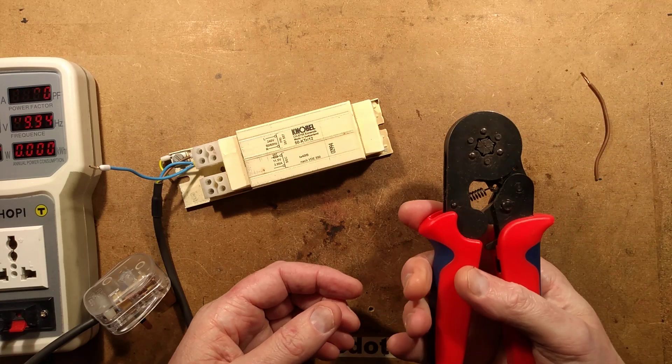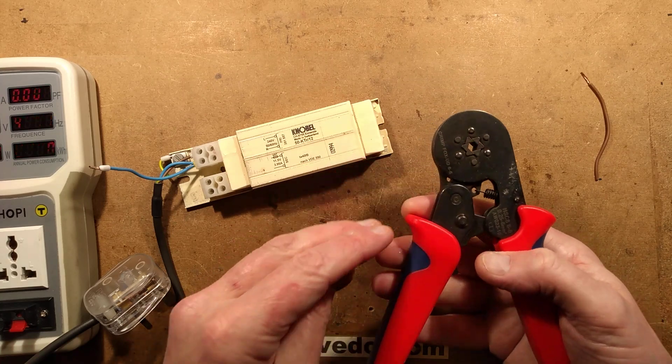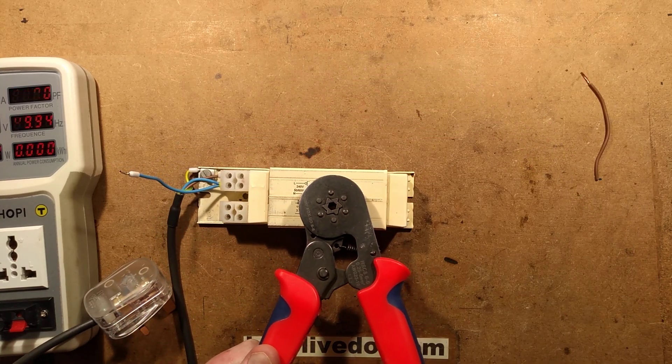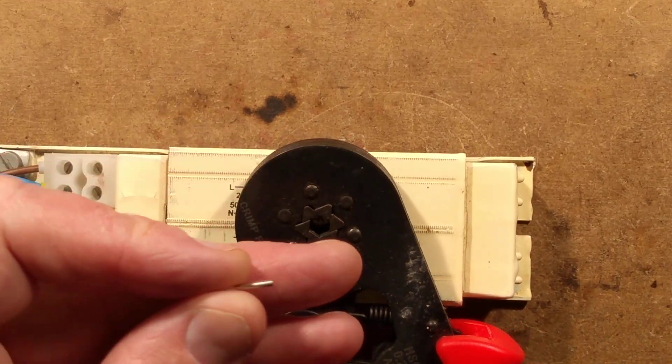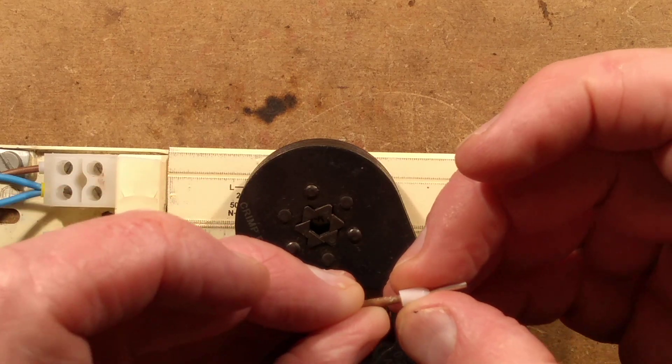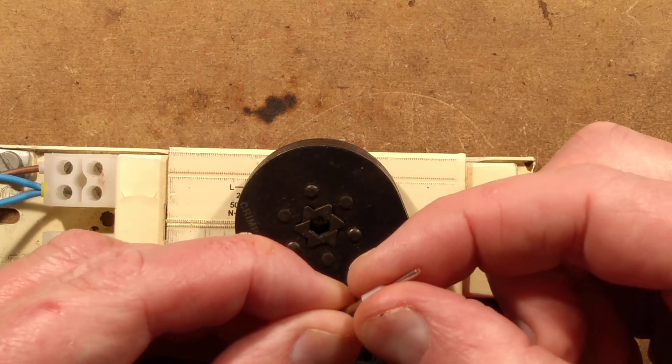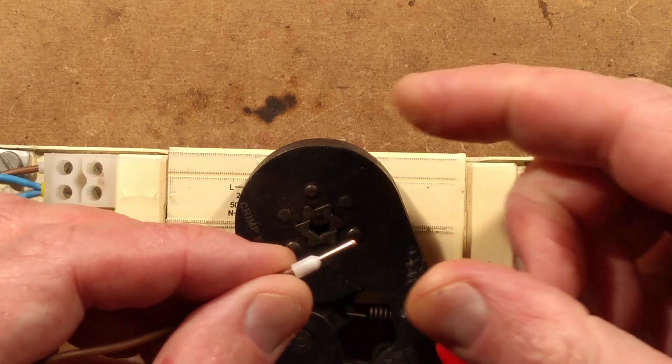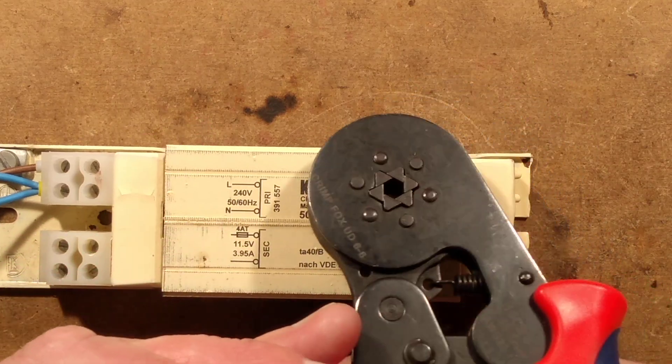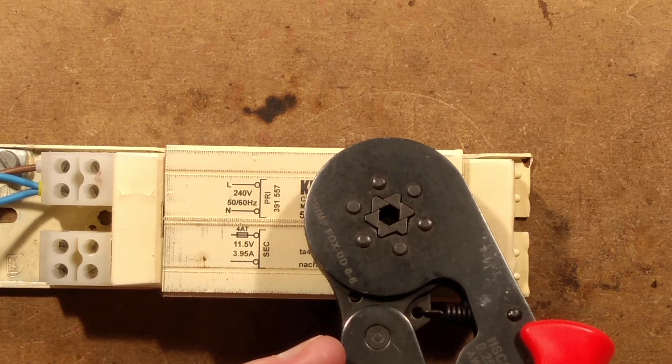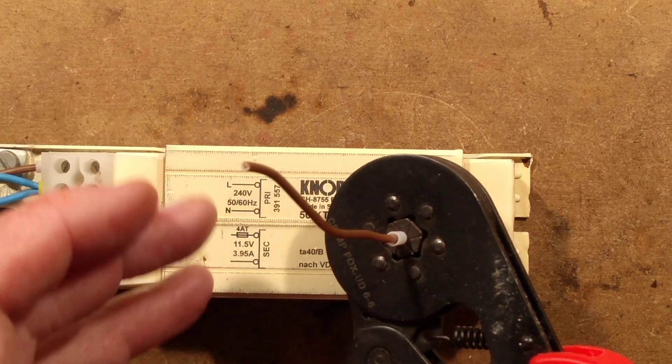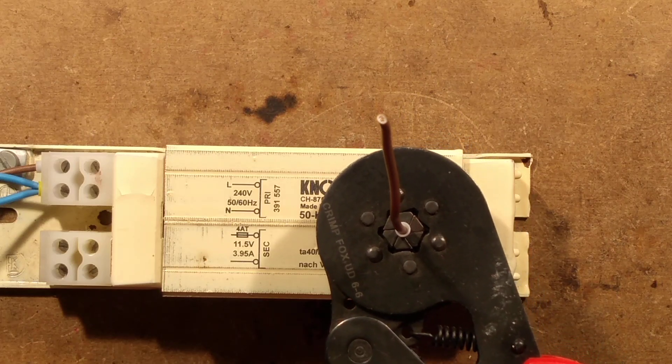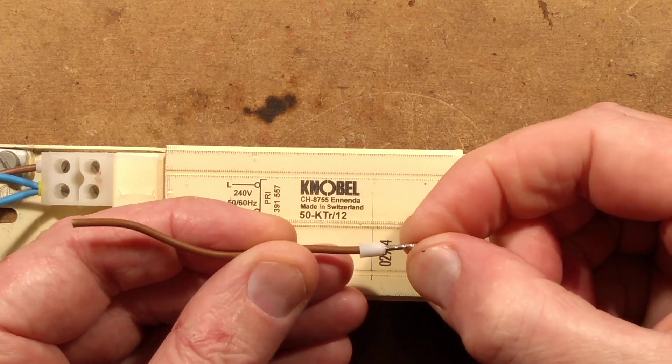And let me show you, I got this crimper from eBay recently because I didn't have a crimper handy. And I wanted to see how good this was. If I zoom down and show you, it's quite neat. These ferrules are designed to, well, I'll thread one over a wire. So here's all the loose strands of the wire. It's designed to keep them all neatly together by threading it over and provide a little shield over the insulation. It looks smart and it provides a good contact area rather than just squishing the strands out under screw terminals. So this tool to crimp them actually has six little wedges that close down like an iris and crimp it. And it's interesting because it's based on pressure. So when I close this down, it doesn't matter the diameter of the ferrule, it will push to a particularly given pressure. And then when you release it, it's put that nice gripping pattern into them.